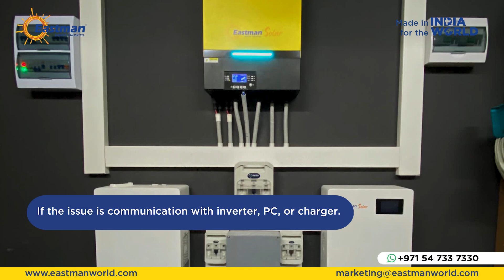The third issue is from the communication cables. If the issue is communication with inverter, PC or charger, first match the communication pins, RS485/CAN, and the protocol. Protocol must be the same for both inverter and the battery. Second, check the module addressing. In a multi-battery system, each battery has a unique ID or address. Duplicate addressing causes communication fault issues.